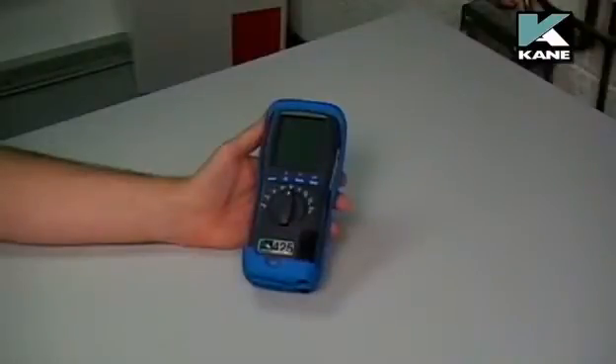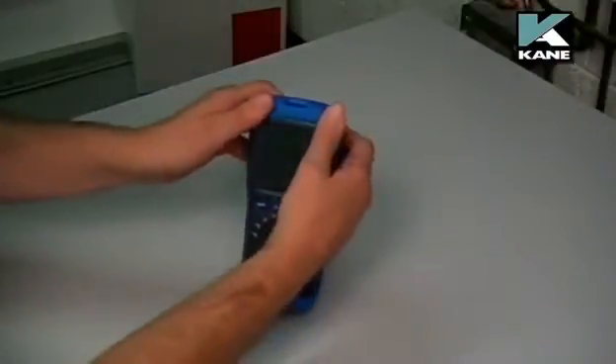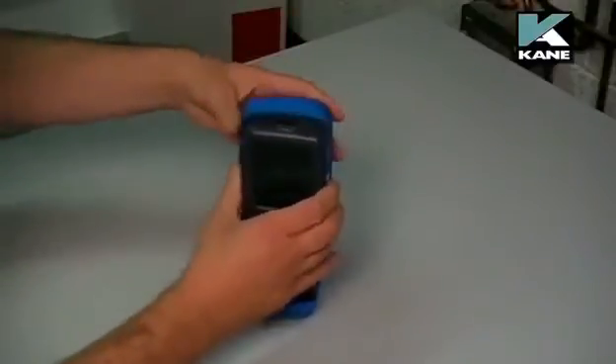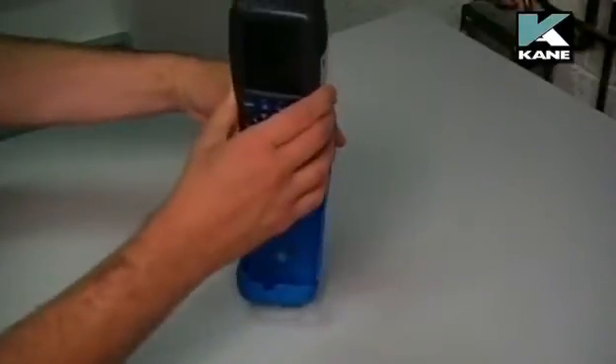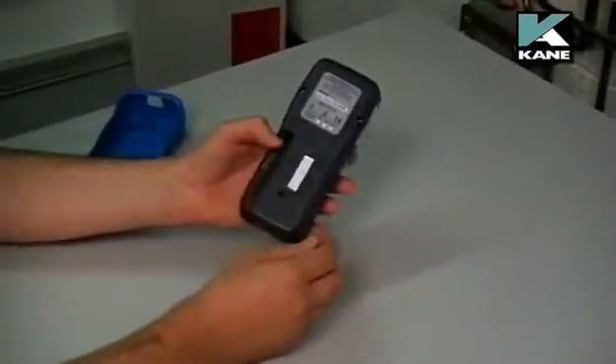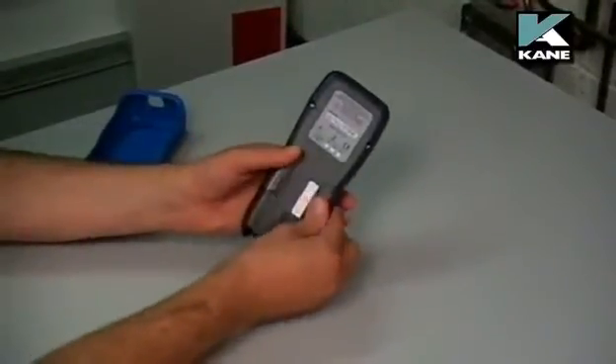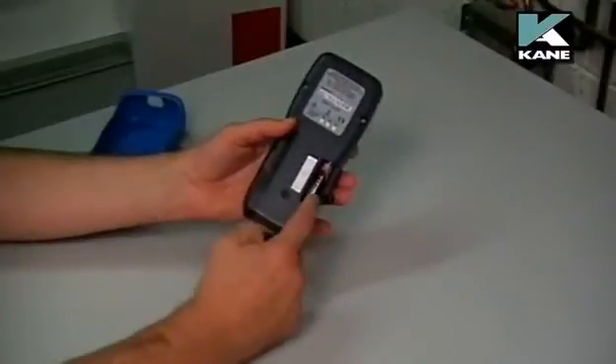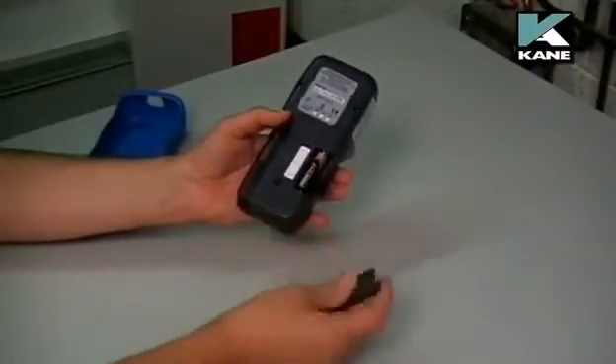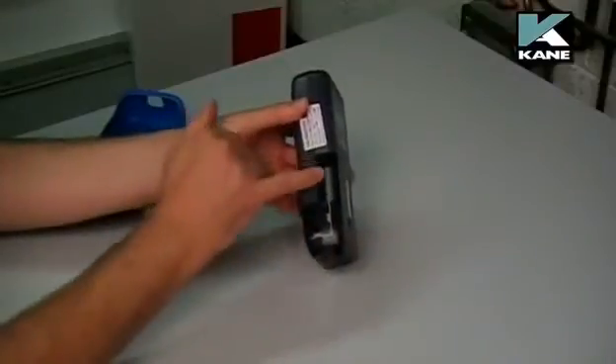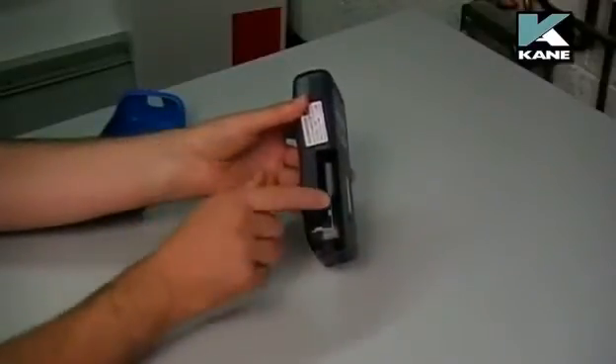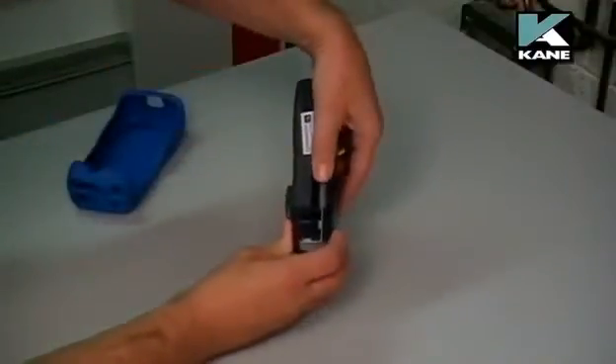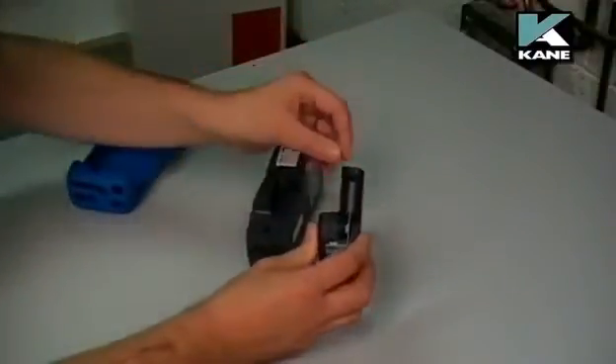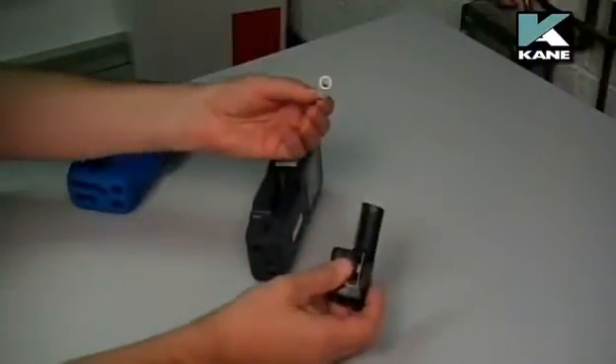To change the batteries or to change the particle filter, you must first remove the rubber boot. The easiest way to do this is to remove it at the top and then pull the analyzer up away from the boot. On the back of the analyzer, this is the battery compartment. Just undo the cover and you can get to the AA batteries. Also on the side of the analyzer you can see the particle filter. To check this we need to remove this whole assembly and you can get to the filter.